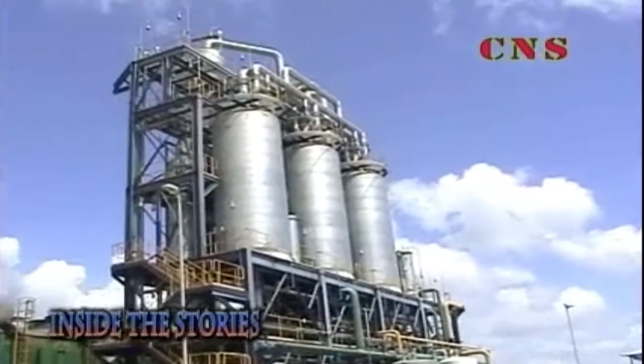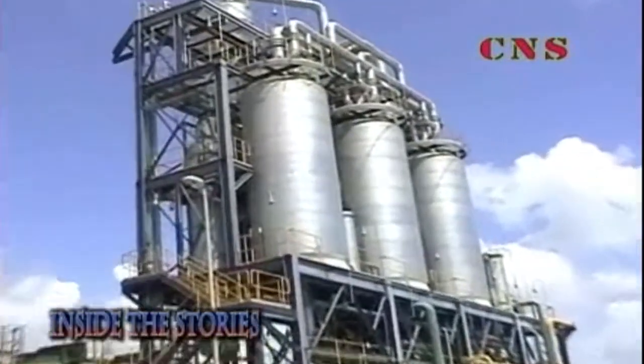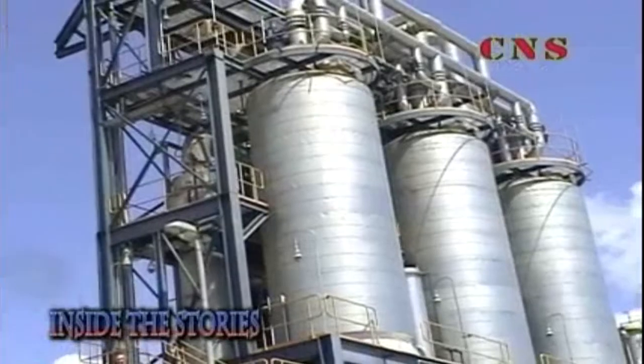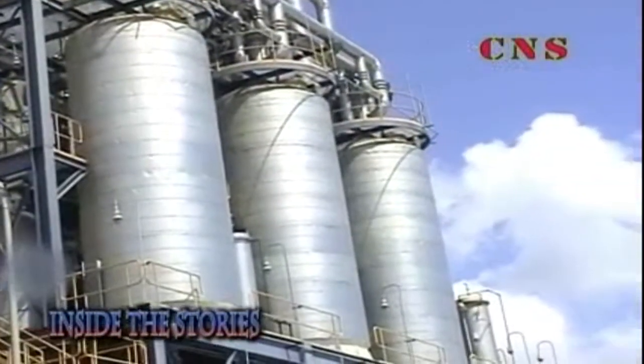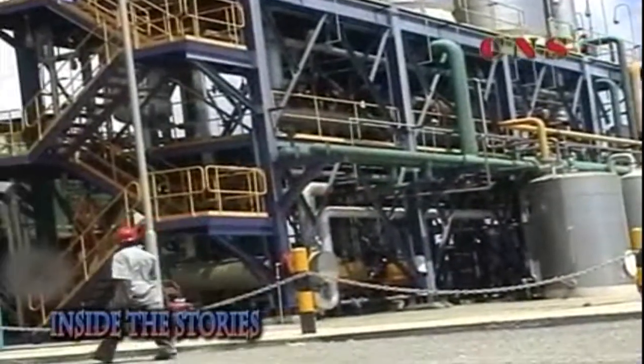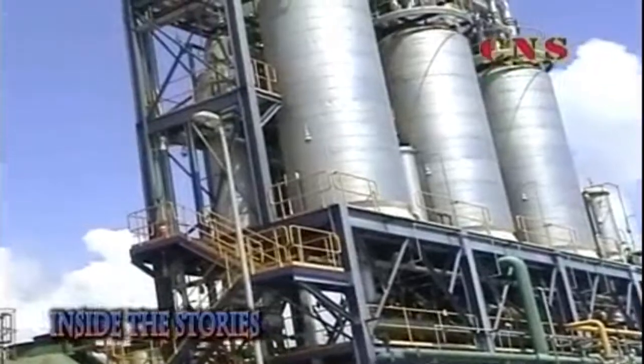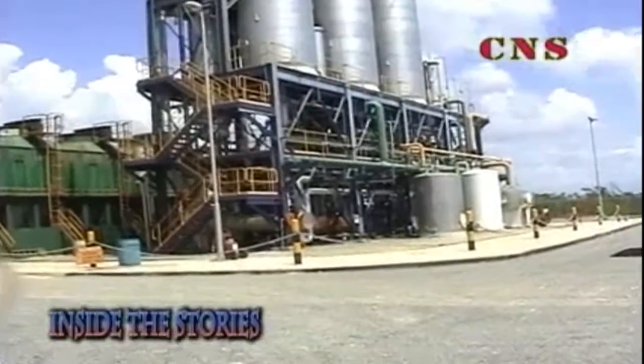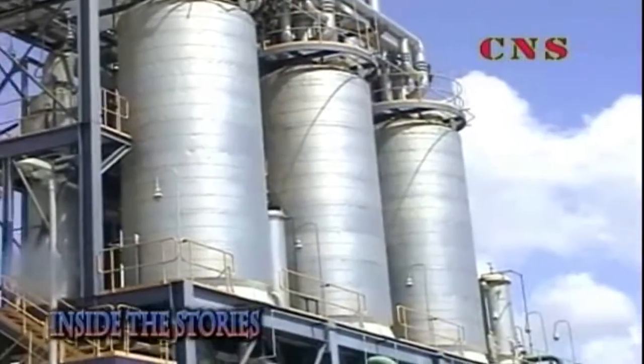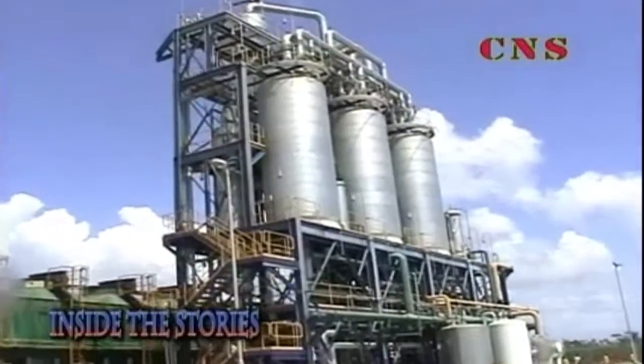What you're looking at is the beginning of the process, dehydration process, and this tank nearest to it here is a hydrous feed tank. Now a pump takes that and pumps it through 2 heat exchangers, then through a heater to the evaporator in order to evaporate the substance, and then to a superheater where it is highly superheated to get rid of the mist, and then to the molecular sieve. In the molecular sieve, what you have is a lot of zeolites. It is full of zeolites, and the molecular sieve we mentioned is those 3 vessels up top, those 3 big vessels. Inside that vessel, as mentioned, is potassium aluminum silicate known as zeolite, and it acts as an absorbent, and this absorbs the water from the hydrous.